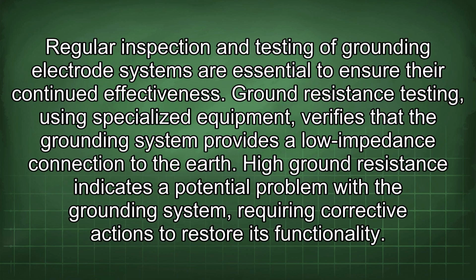Regular inspection and testing of grounding electrode systems are essential to ensure their continued effectiveness. Ground resistance testing, using specialized equipment, verifies that the grounding system provides a low impedance connection to the earth. High ground resistance indicates a potential problem with the grounding system, requiring corrective actions to restore its functionality.